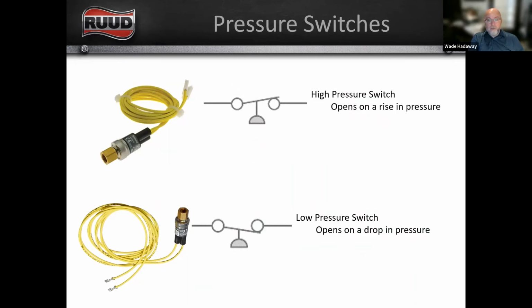So we're going to move on to pressure switches. I mentioned pressure switches a little bit earlier, right? So this is the symbol for a pressure switch. On the top switch, you can see that little semicircle. If it were to push up, it would push that switch open, right? So that would be a high pressure switch, and that high pressure switch opens on a rise in pressure.